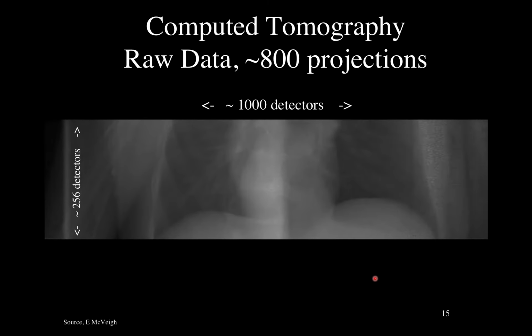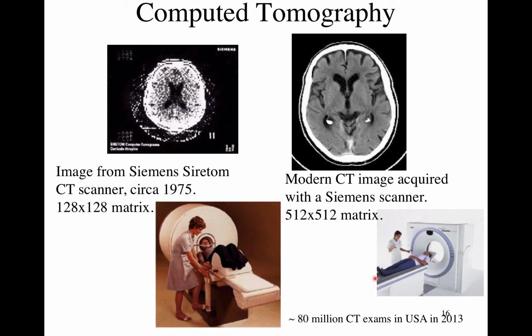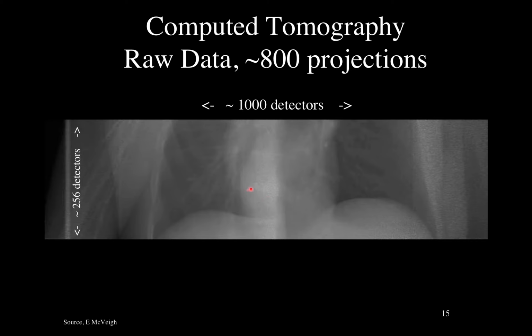The essential thing to understand is, if we stop this at one point, the brightness here corresponds to the amount of attenuation. So it's not actually an X-ray image in the sense that a dark shadow corresponds to attenuation. It's been inverted, so brightness means I've got a lot of attenuation. At any one point on this detector, the relative attenuation that I've measured there is from the line integral through the object in this direction.